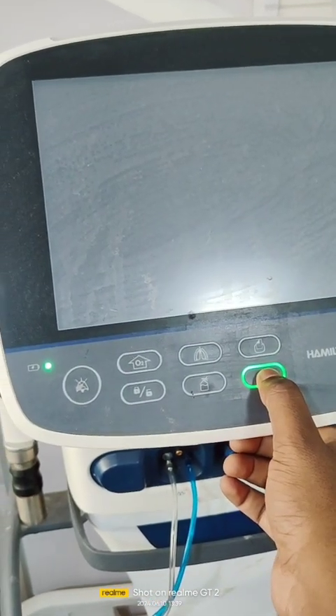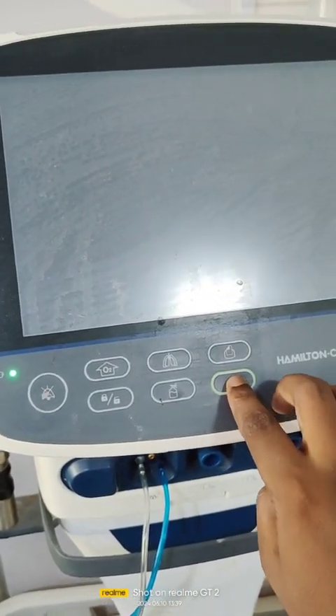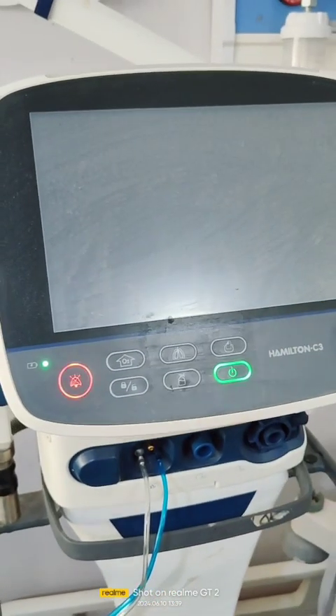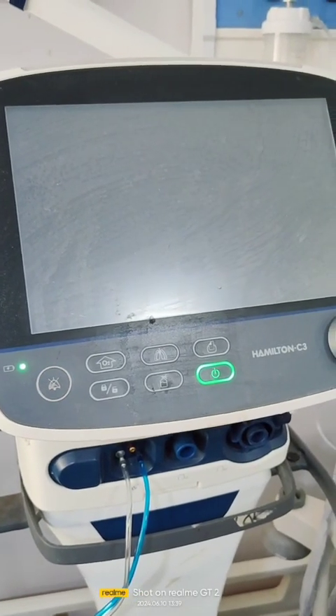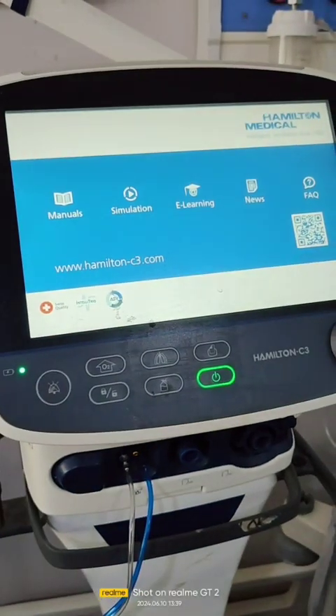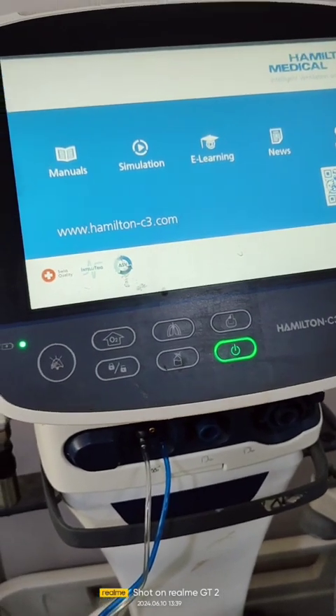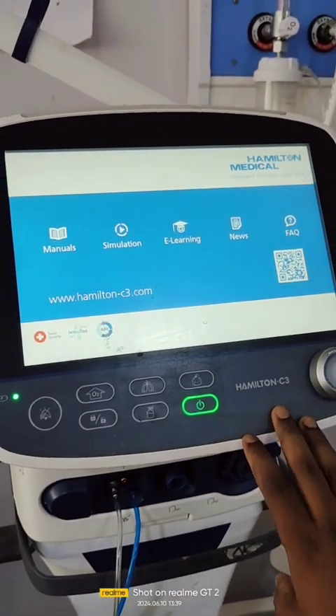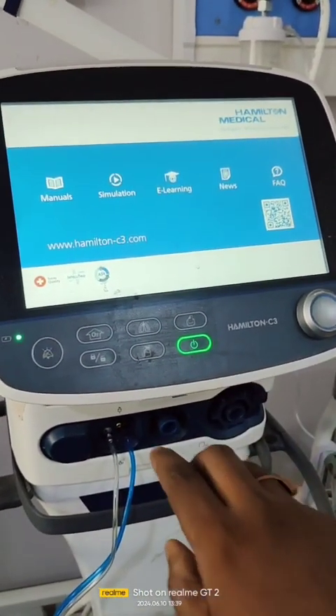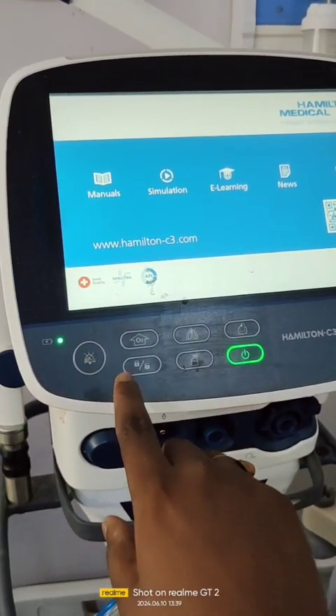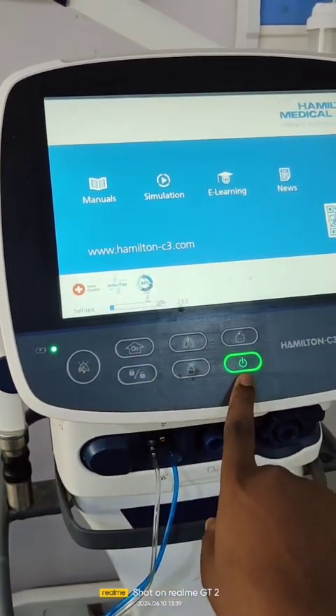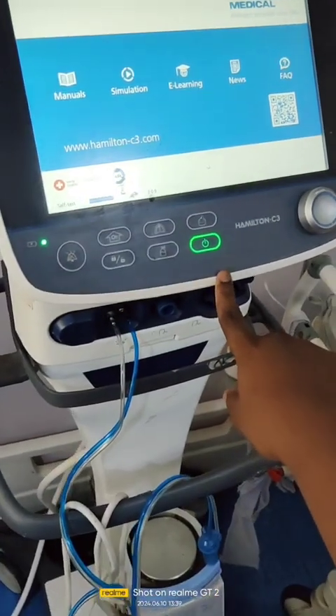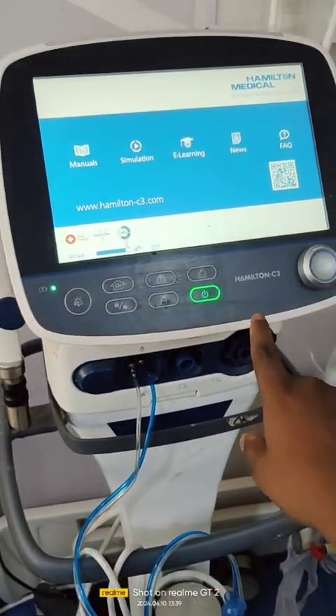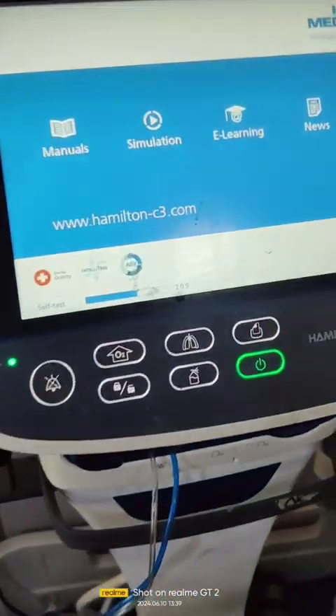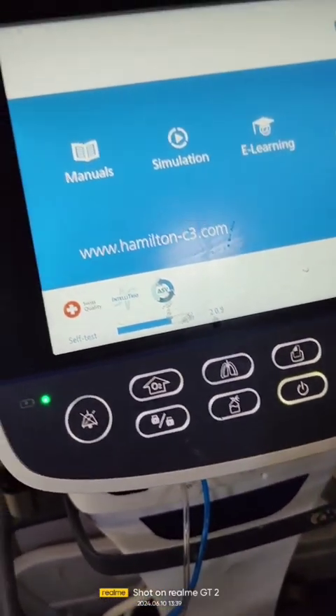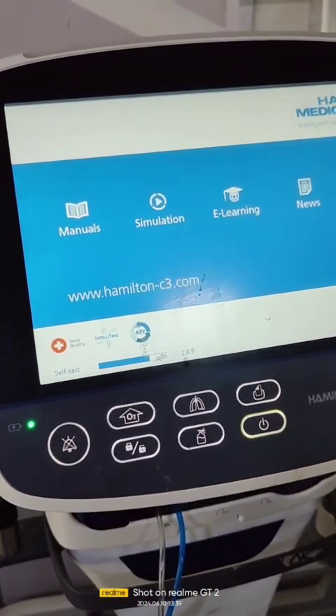Complete switch off, and now we restart the ventilator system. It will be getting on. We just have to wait. We just have to operate and wait until the system reboots. So regarding this ventilator, we have to check one by one, and whether the keyboard and panel are all good or not. Because it is out of the part, we have to check the machine first of all. Okay, next this one. So next, see here, wait because it is still rebooting.